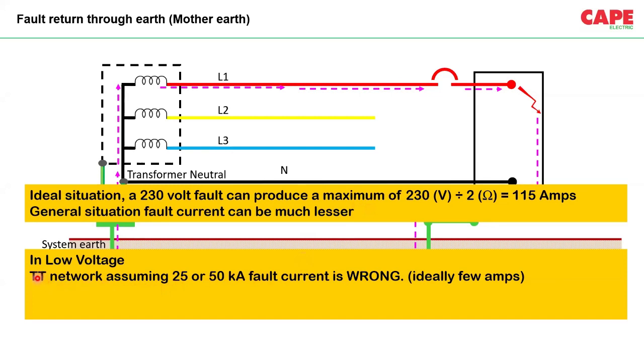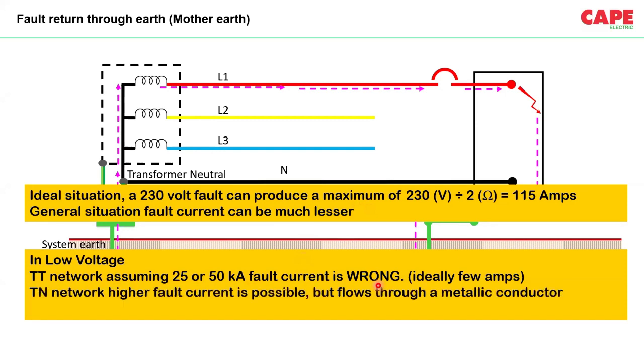Now, for your information, in a TT network, assuming 25 or 50 kiloampere fault current is wrong. Several times people think that large fault current is going to flow. The network is TT and low voltage. This is absolutely wrong. Ideally, only a few amps is possible because you have 1 plus 1 ohm, 2 ohm, or much more resistance in this particular loop.